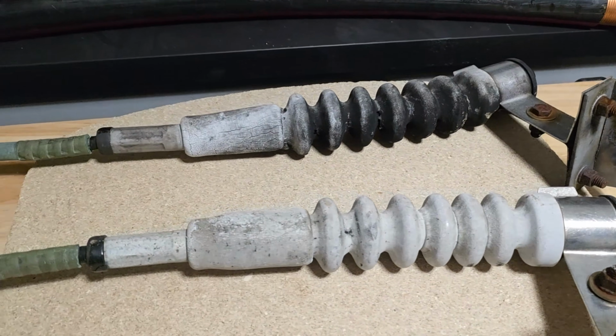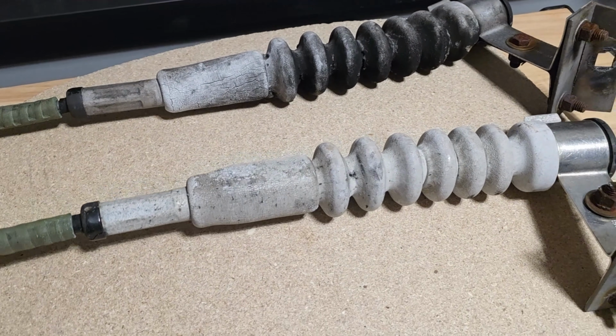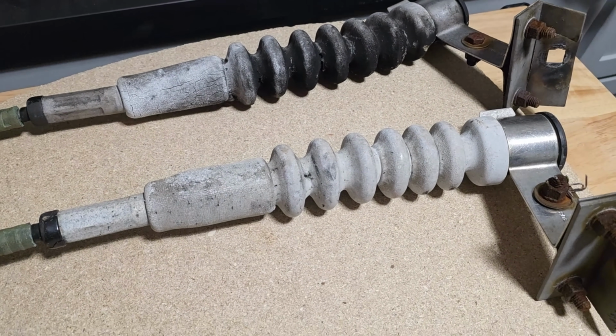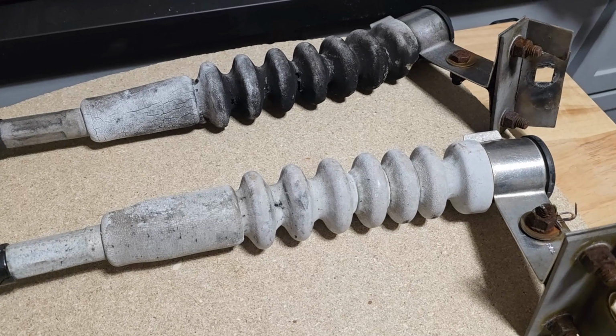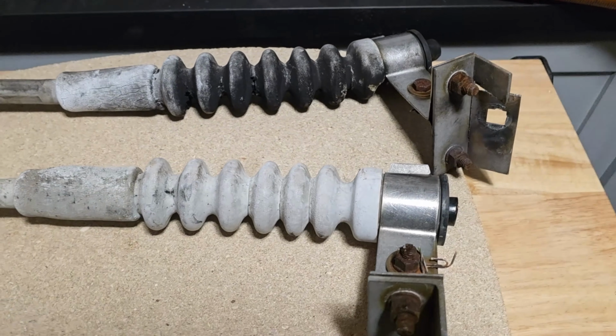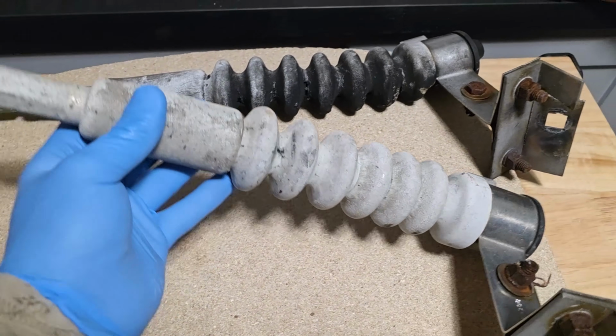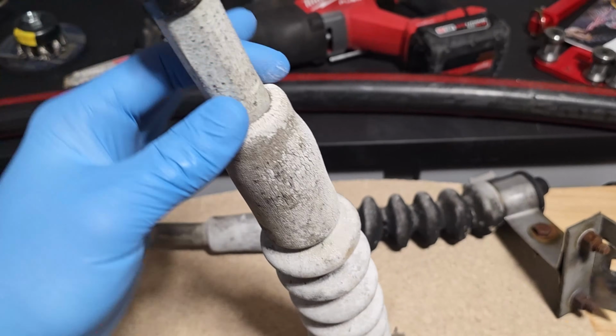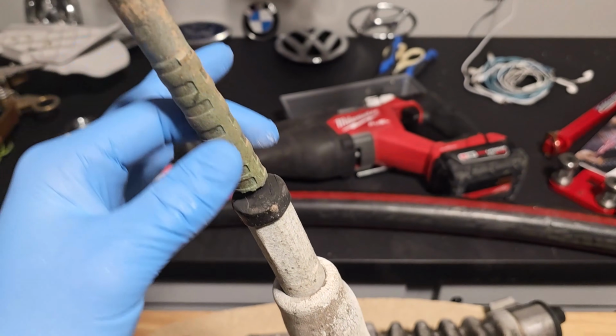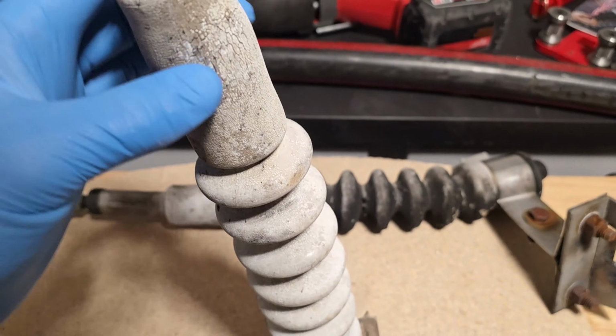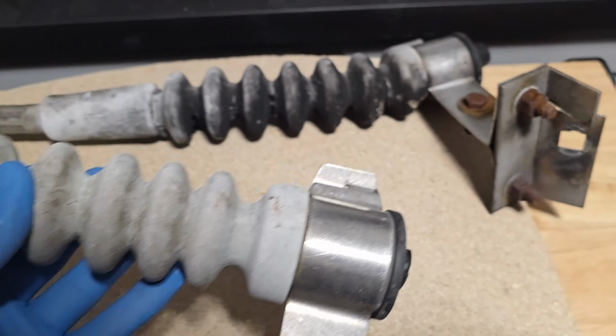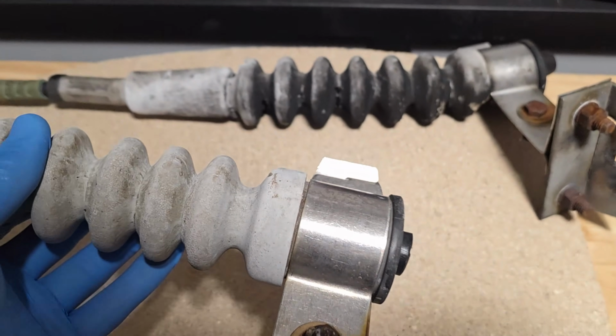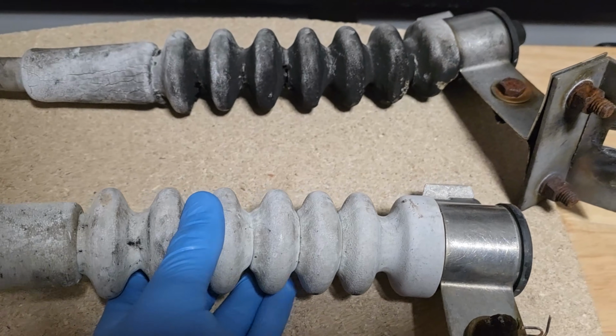First thing I want to mention for the viewers that are linemen - I'll switch to different lingo for the non-lineman viewers - but when you're doing terminations, one of the most important things is not allowing water to get into the termination. If water bleeds down inside that cable, the freeze-thaw is going to wreak havoc on it.